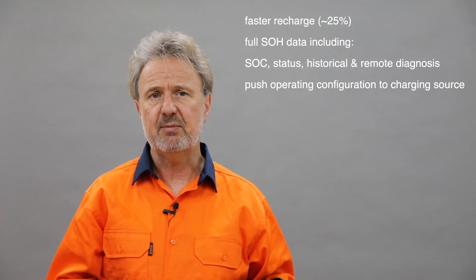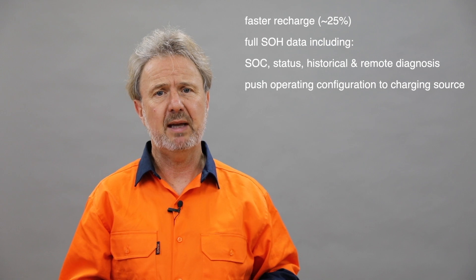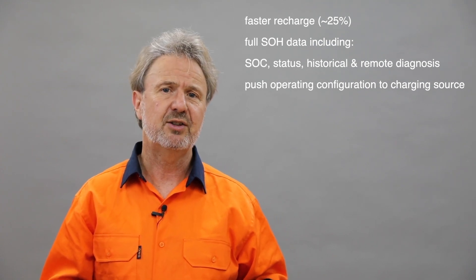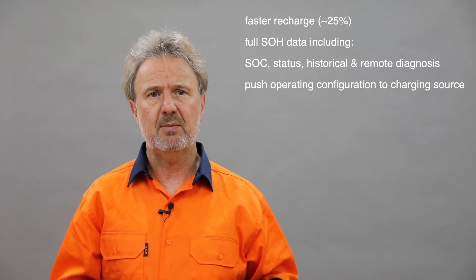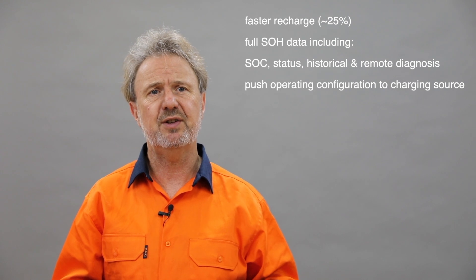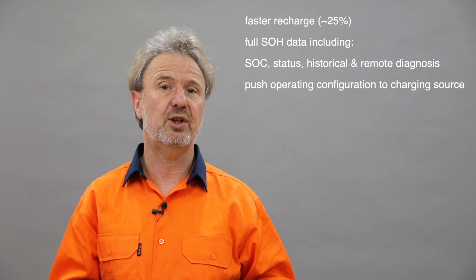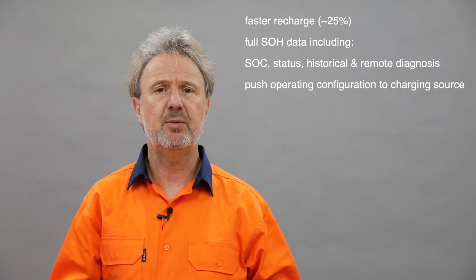Let's look at some of the pros and cons. Managed battery — what are the pros of having a comms management system? A communication system that allows the battery to talk to the charging source and vice versa. One of the advantages, particularly with lithium iron phosphate batteries, is faster charging. Typically you'll get more than 25% faster charging with a managed battery, because of the ability to adjust the charging profile to suit the characteristics. Because the BMS built into the battery is constantly measuring temperature and voltage of the cells, it allows you to push the edge a bit more in terms of rate of charge compared to having no communication.